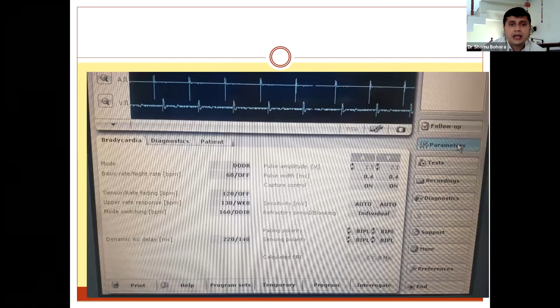However, if you see the ECG, it's pacing faster. So that is not only 10 seconds as recorded here. So what must have happened? The atrial tachycardia rate would have been lower than 160. That is why the mode switch did not occur. And therefore, the upper tracking rate pacing would have occurred, which was not normal for this patient. And the second thing that can happen is an atrial arrhythmia may not be documented due to undersensing during the atrial tachycardia itself. So the mode switch did not occur.